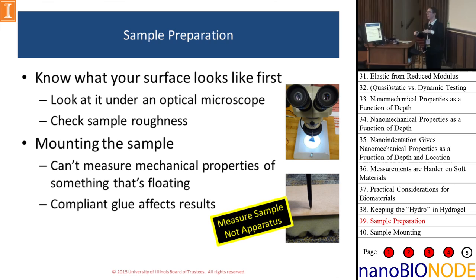And never ever use carbon tape for nano indentation. It is way too compliant. All you'll measure is the glue, the carbon tape there. So don't use carbon tape. Measure your sample, not your sample mounting.